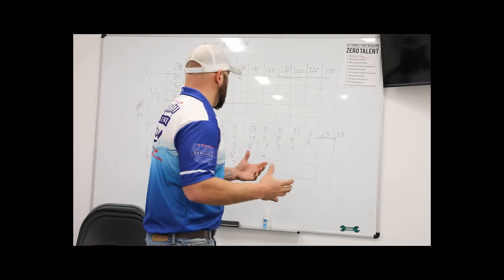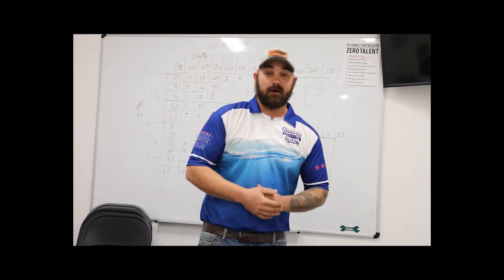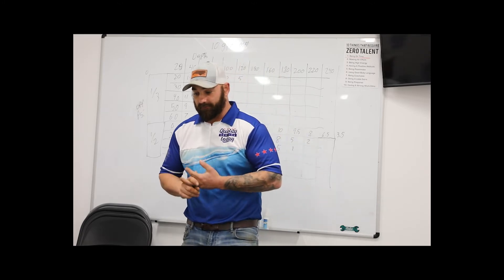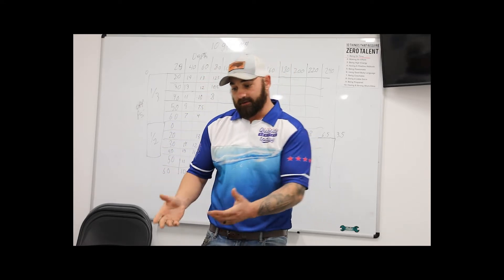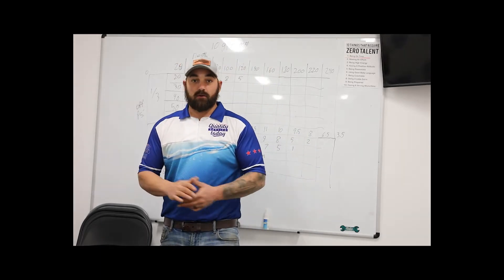Today I'm going to go over a roughly brief description of how to size a well pump. Sizing a well pump is really important for multiple reasons. The well pump does not make your pressure. The biggest misconception that a lot of people have, they go to box stores and they're like, oh well, there's a half horse there that I pulled out of my well, I'm going to put a one horse back because I want plenty of water pressure. It doesn't make your pressure. Your pressure tank makes your pressure. I got a video how to adjust your pressure tank and the pressure. Go watch that one.